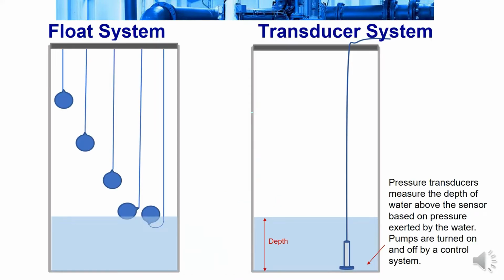The float system that we see on the left here is the backup system for the Portage lift station. What the Portage lift station uses as a common system is the transducer system, which is simply a pressure transducer that is measuring the water pressure above that sensor. The higher the pressure, the more pumps are turned on at a predetermined value.